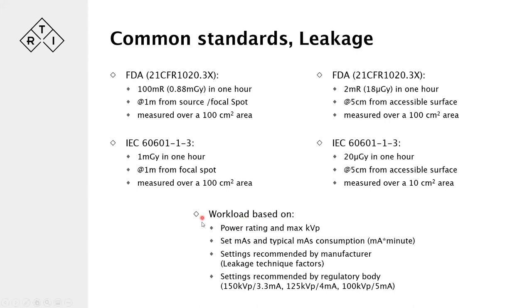We need to normalize our measurements based on the power rating and maximum kVp of the machine, referring to the set mAs and typical mAs consumption. Leakage technique factors are provided by the manufacturer, but there are also exposure settings recommended by different regulatory bodies depending on the country, which are used for leakage evaluations.